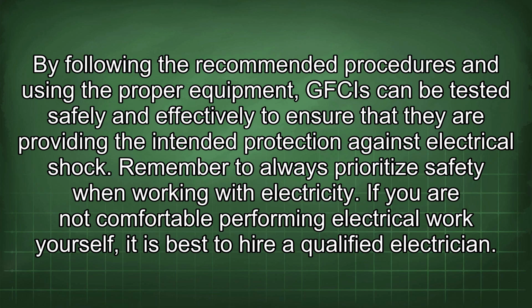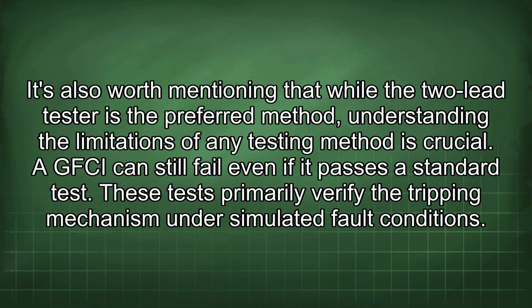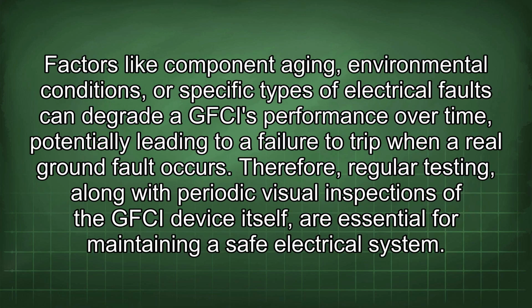Remember to always prioritize safety when working with electricity. If you are not comfortable performing electrical work yourself, it is best to hire a qualified electrician. It's also worth mentioning that while the 2-lead tester is the preferred method, understanding the limitations of any testing method is crucial. A GFCI can still fail even if it passes the standard test. These tests primarily verify the tripping mechanism under simulated fault conditions. Factors like component aging, environmental conditions, or specific types of electrical faults can degrade a GFCI's performance over time, potentially leading to a failure to trip when a real ground fault occurs.